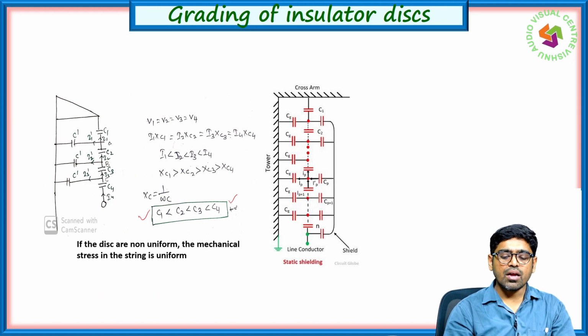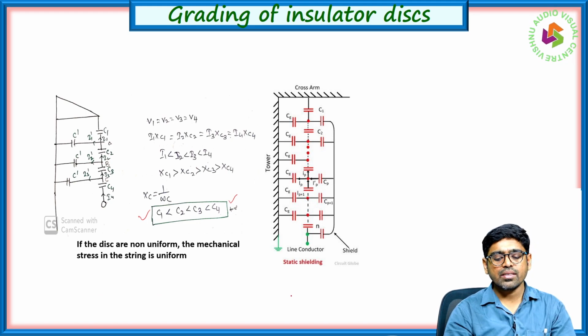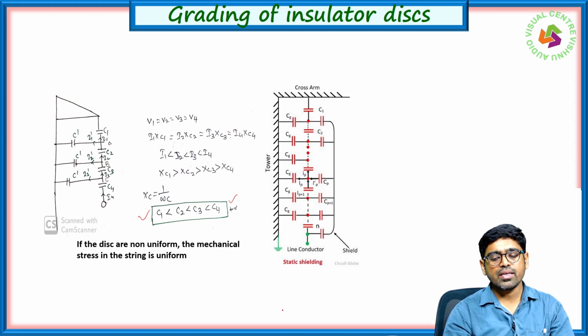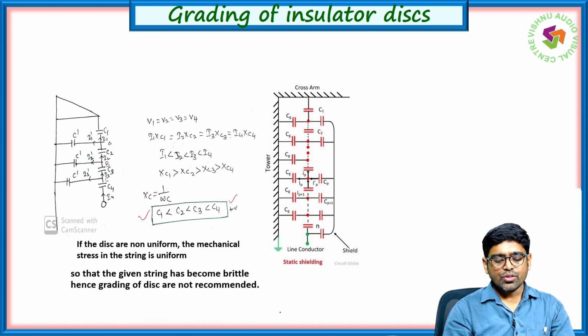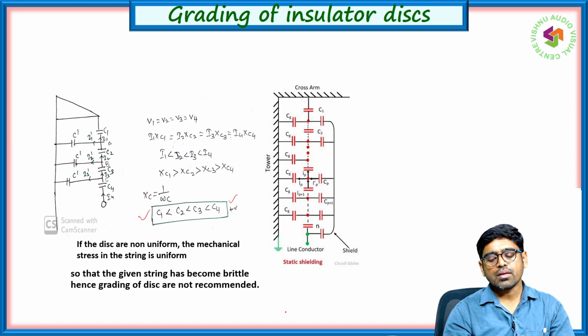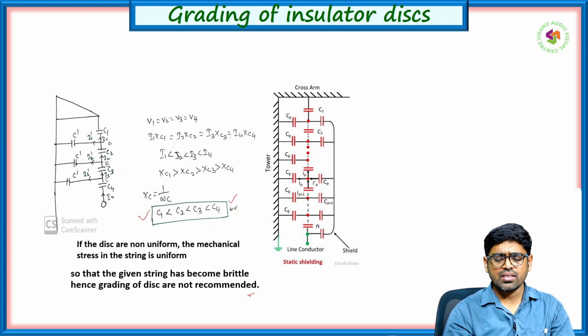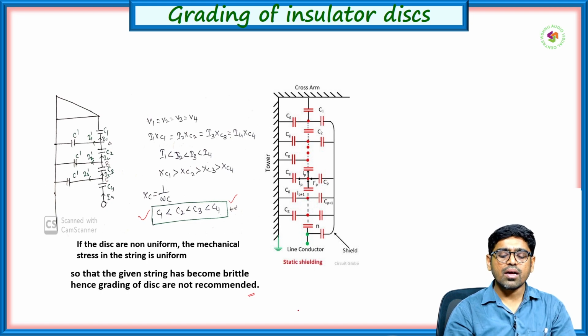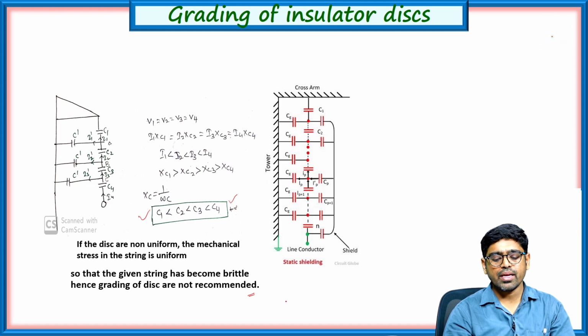If the discs are non-uniform, the mechanical stress in the string is non-uniform, and so the given string becomes brittle, hence the grading of the discs is not recommended. So these are the disadvantages if you recommend the grading of the insulator.